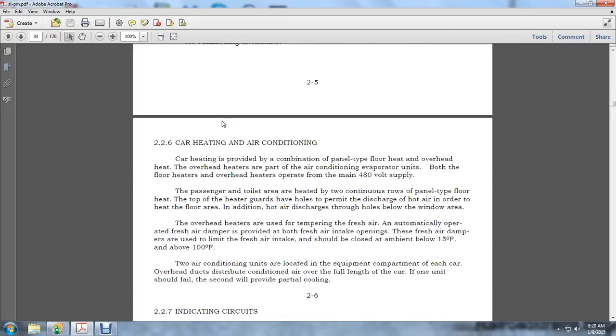226, car heating and air conditioning. Car heating is provided by a combination of panel floor heat and overhead heat. The overhead heaters are part of the air conditioner evaporator units. Both the floor heaters and overhead heaters operate from the main 480-volt supply. Passenger areas and toilets are heated by continuous rows of panel-type floor heaters. The heater guards have holes to permit the discharge of hot air in order to heat the floor area. In addition, hot air discharges through the holes in the window area below the windows. The overhead heaters are used in tempering fresh air.